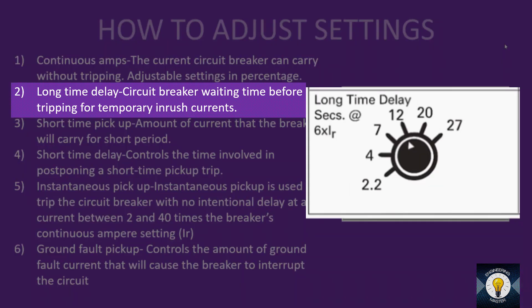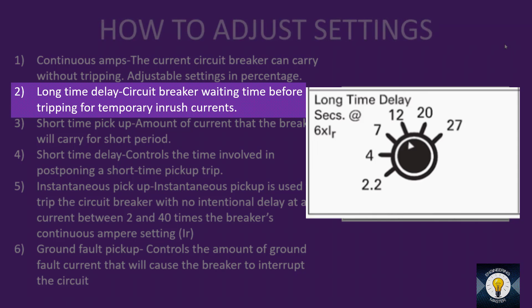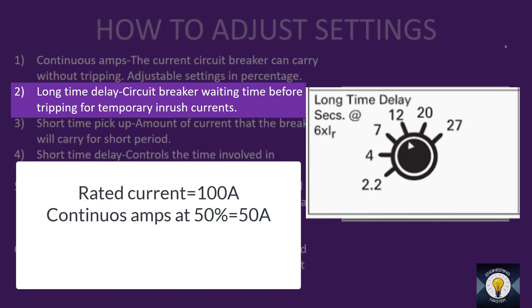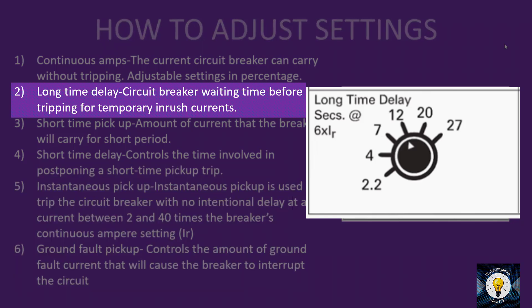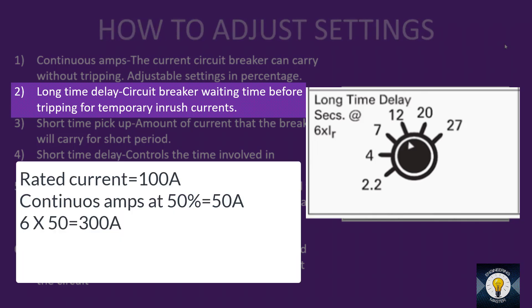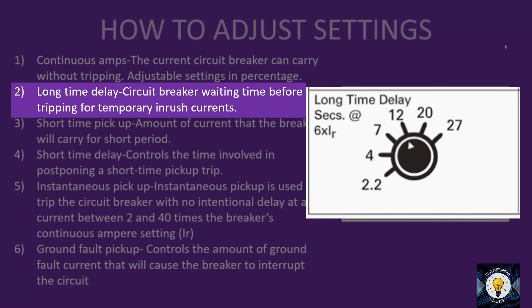Long time delay is the circuit breaker's waiting time before tripping for temporary inrush current. It is expressed in seconds at six times the continuous amps. For example, if the breaker is rated 100 A and the continuous amp switch is at 50%, continuous amps = 50 A. Six times 50 A is 300 A. Up to 300 A, you can adjust the tripping delay from 2.2 to 27 seconds using this switch.